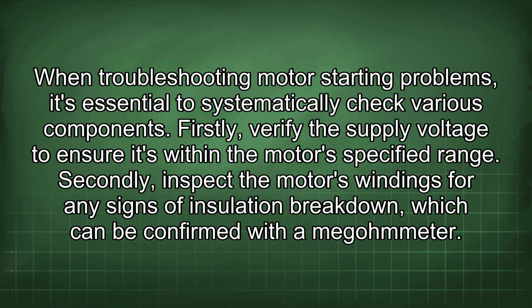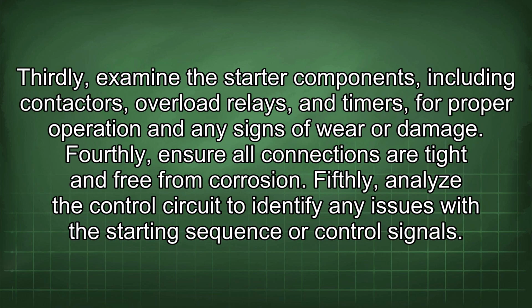When troubleshooting motor starting problems, it's essential to systematically check various components. Firstly, verify the supply voltage to ensure it's within the motor's specified range. Secondly, inspect the motor's windings for any signs of insulation breakdown, which can be confirmed with a megohmmeter. Thirdly, examine the starter components, including contactors, overload relays, and timers for proper operation and any signs of wear or damage. Fourthly, ensure all connections are tight and free from corrosion. Fifthly, analyze the control circuit to identify any issues with the starting sequence or control signals.